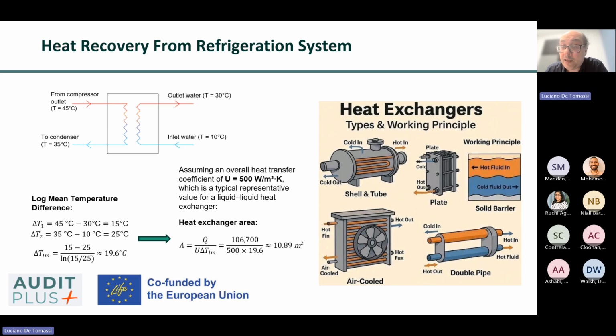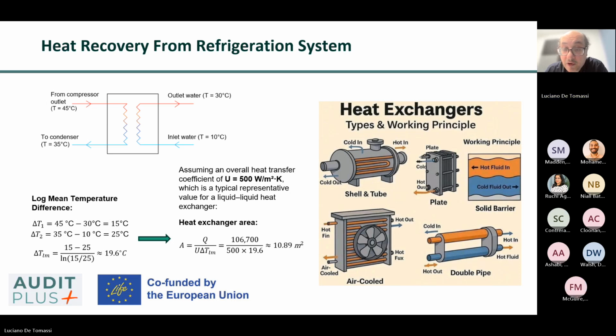Plate heat exchangers are widely used where high thermal efficiency and compactness are required. They consist of stacked corrugated plates that create alternating channels for refrigerant and water. Their high turbulence promotes excellent heat transfer, allowing for smaller temperature differences between streams. They are particularly effective in water-based heat recovery from refrigeration systems, but can be more sensitive to fouling and may require better fluid quality control.